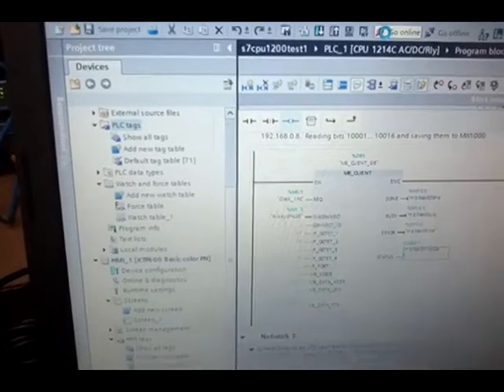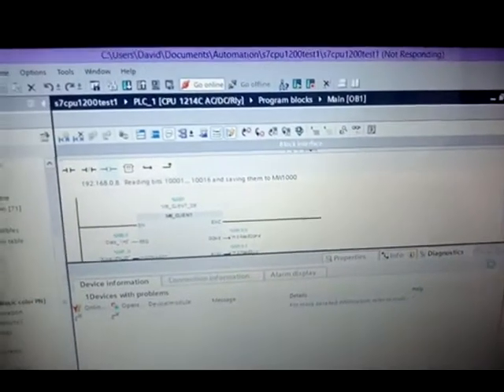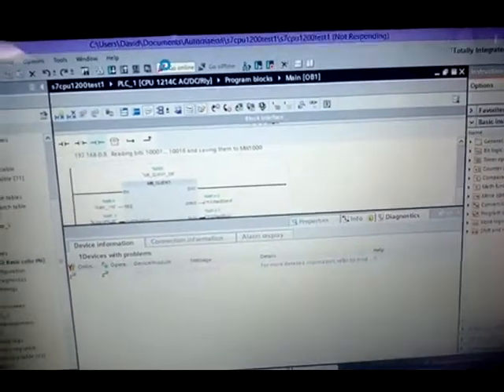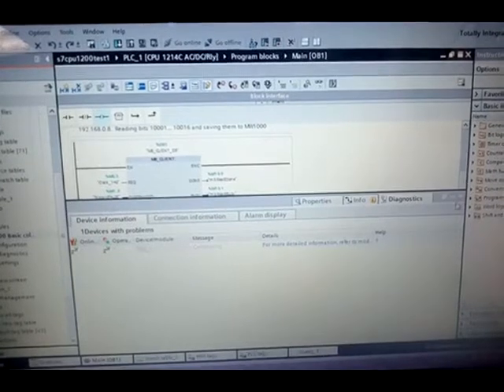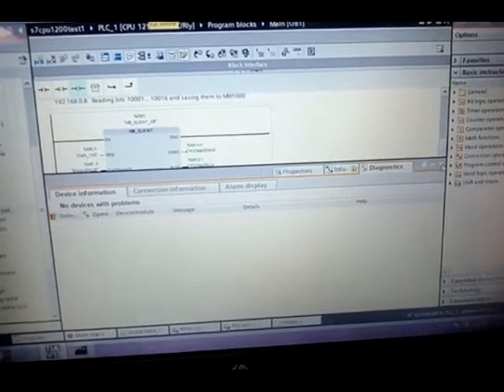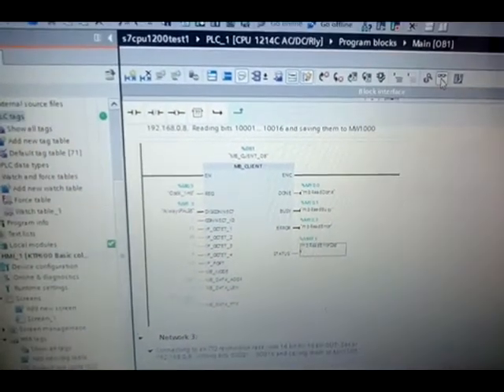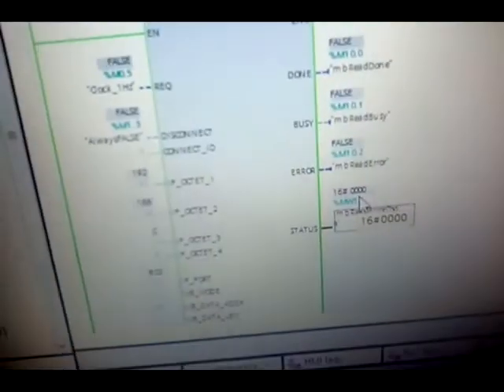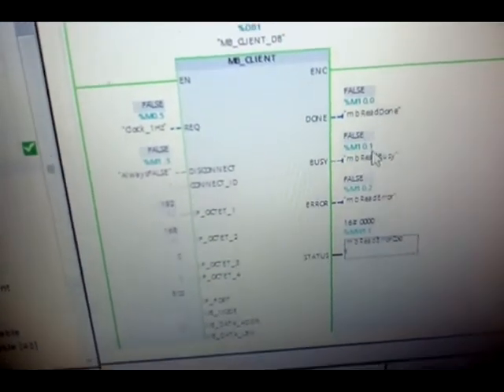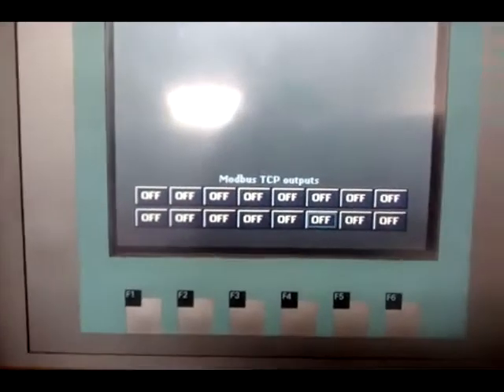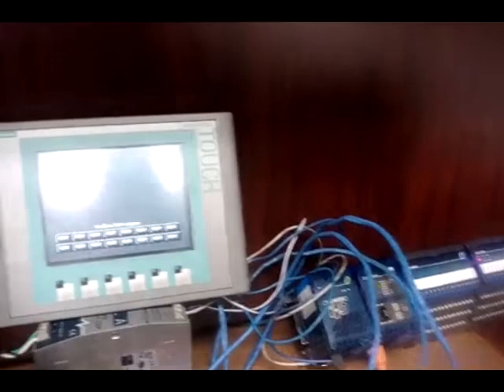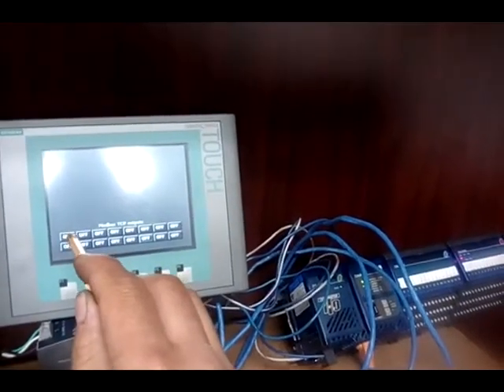Trying to go online here. It's taking a while, but I want to show you what the—I don't know if you guys can see it on your screens, but this is going on and off, reading and writing. So the read is done on the positive flank of the one hertz clock pulse, and then the write is done on the negative flank of the one hertz clock. And I done this by inverting a bit and then using the other bit for the write. So I am refreshing every second.